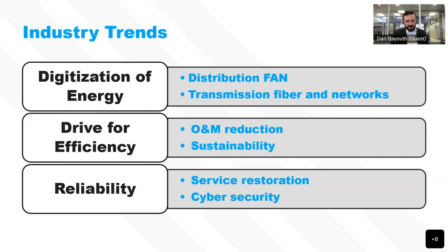And one of the hindrances to automation has been older equipment in the electric grid communication system. Utilities like to put stuff out there and run it for as many years as they can get out of it, because it is disruptive to do these upgrades. And some of those legacy devices are not easy to automate. They just weren't designed for it. You don't have API access into things, or you might not even have a central management platform. You just have discrete devices in the field because when this was installed 15, 20 years ago, this is the device we used, and it worked really well to get a little bit of information out of the device every so often.